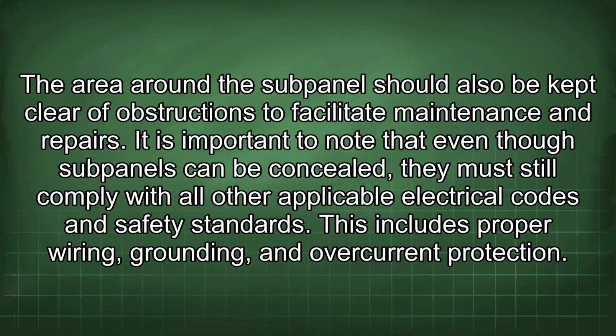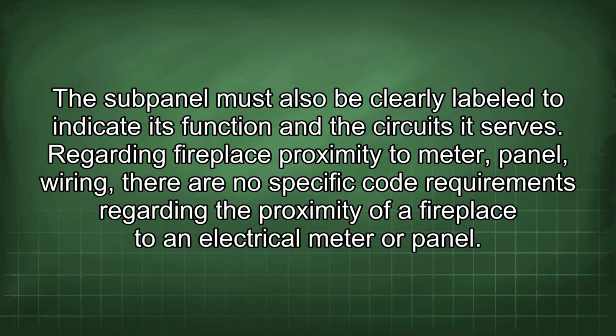The area around the subpanel should also be kept clear of obstructions to facilitate maintenance and repairs. It is important to note that even though subpanels can be concealed, they must still comply with all other applicable electrical codes and safety standards. This includes proper wiring, grounding, and overcurrent protection. The subpanel must also be clearly labeled to indicate its function and the circuits it serves.